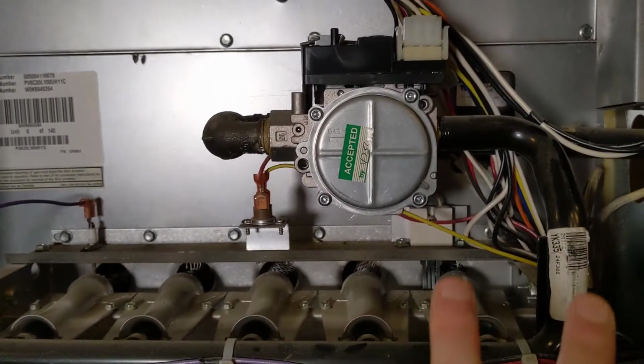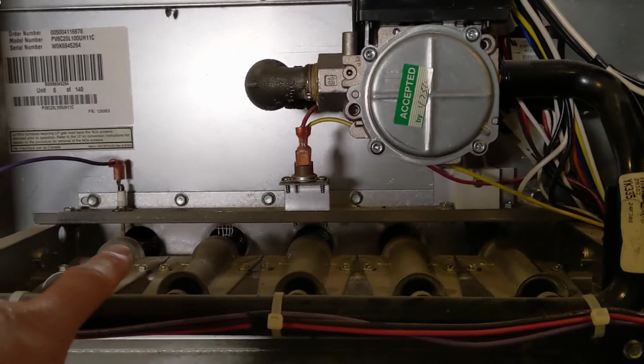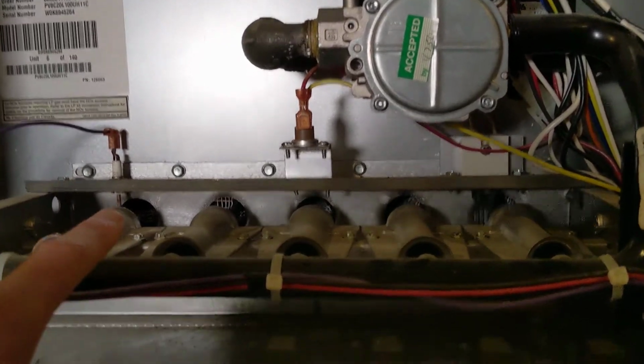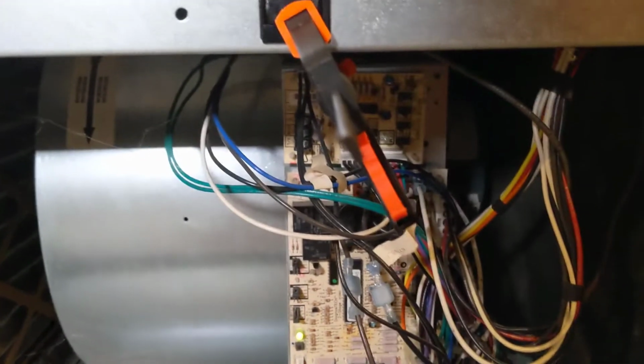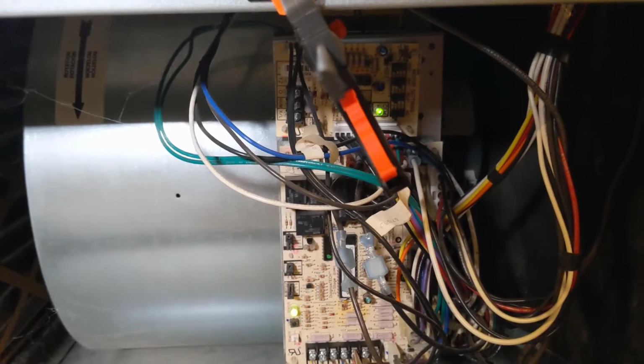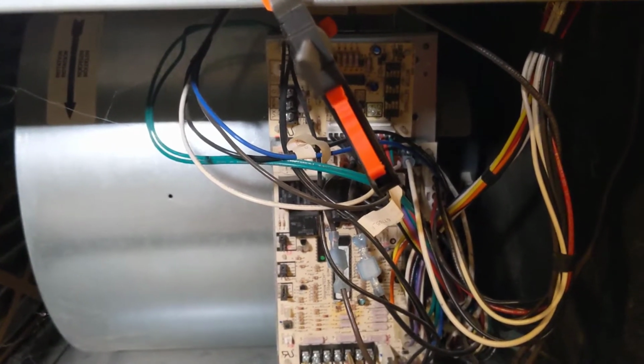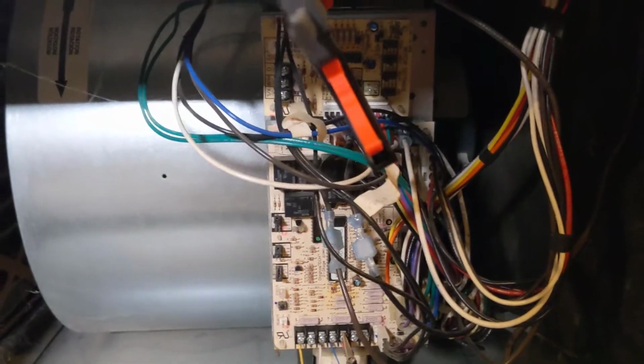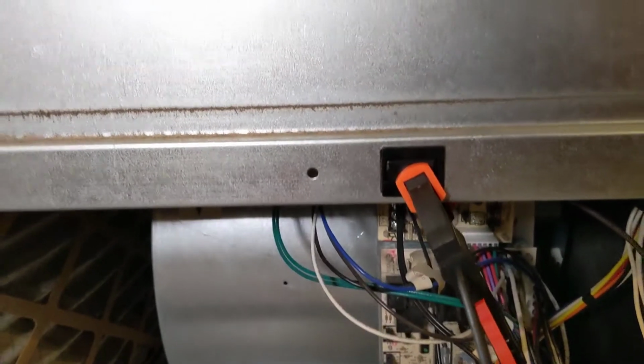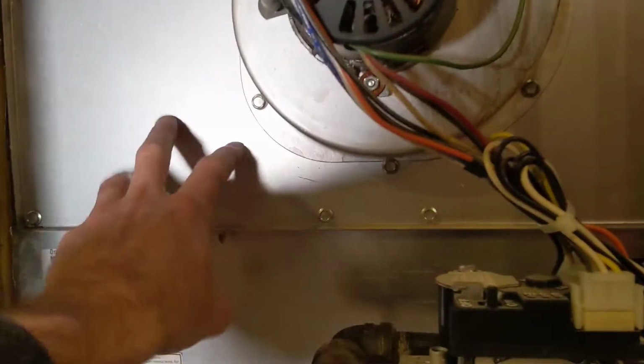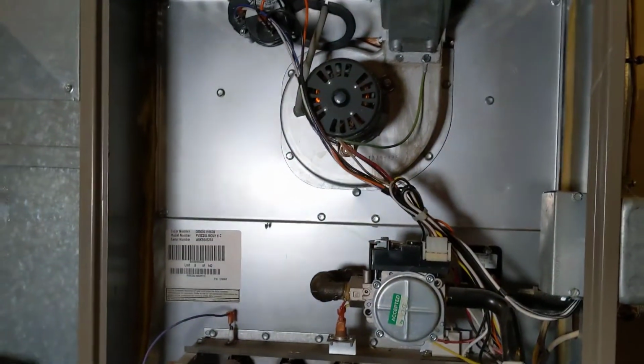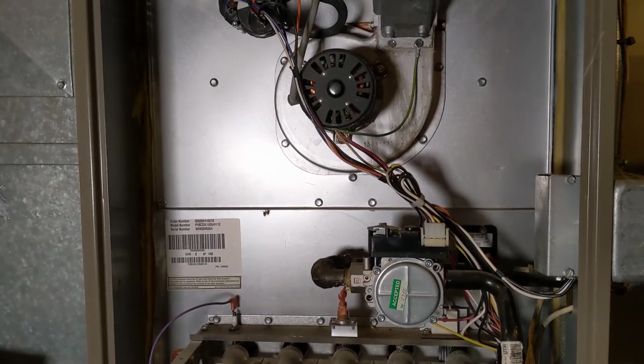Okay, so at this point now we have full combustion. We have our flame sensor detecting a flame. The next step is down at the very bottom, and that's the blower motor. The blower motor is going to fire once it knows we have combustion, and once we've heated up the chamber to a proper temperature, then we can start blowing the air. Now the blower, usually on an updraft furnace, starts at the bottom, and it blows the air up in the back of this heat exchanger here, and up through the plenum, and then distributes it out to the different ducts. So that's essentially how a furnace works. Not too difficult. So let's watch this thing in action.